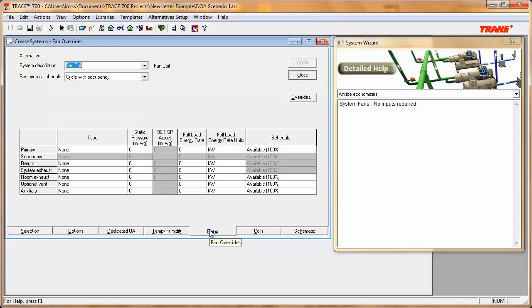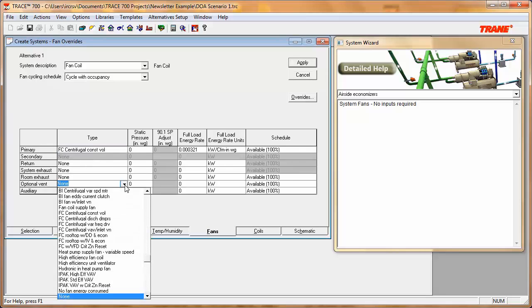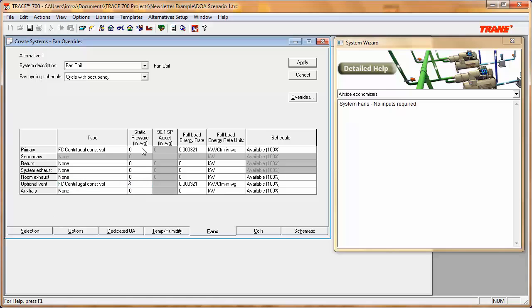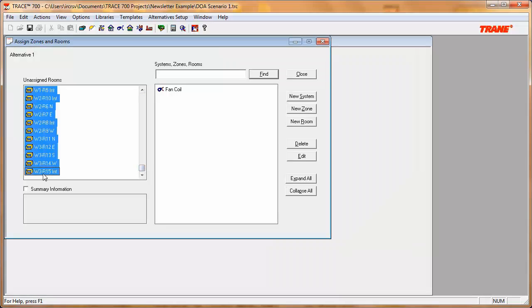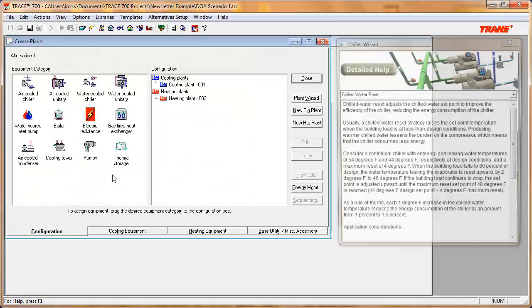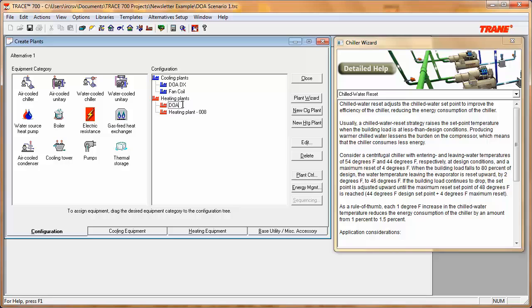Clicking Apply, we go into the Fans tab to select the fan for our fan coil and the fan for our DOA. I'll select the fans and enter the static pressure for both. Then we go into Assign Rooms to assign all rooms to that system. Next, in Create Plant, we set up two cooling plants — one dedicated for the dedicated outdoor air coil and the other for the fan coil — and two heating plants, one for the DOA and one for the fan coil.